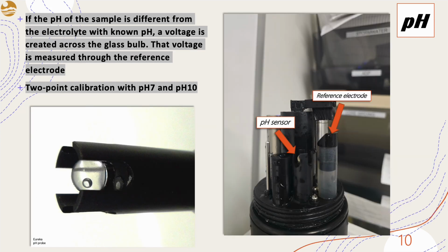pH is measured with a pH sensor and a reference electrode. The pH sensor is a small glass bulb filled with an electrolyte of a known pH. If the pH of the sample, which is water, is different from that electrolyte, a voltage is created across the glass bulb. That voltage changes predictably with the pH of the sample water and is measured through the reference electrode. The reference electrode contains an electrolyte separated from the sample water not by a glass bulb, but by a material that is microporous, and in this case is Teflon. It allows the electrolyte to contact the water without being quickly diluted by it.